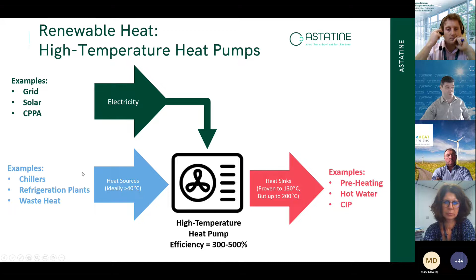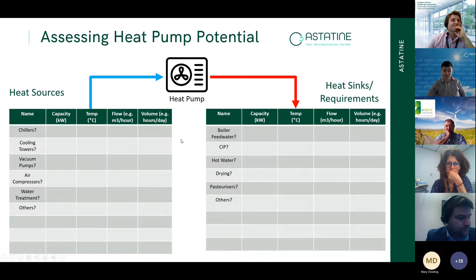I would say on the dairy facilities, these are very typical of the sources and sinks that we find. So on the sources, we find things like chillers, cooling towers, vacuum pumps, air compressors, water treatment plants, and then we quantify what amount of heat we can absorb from those different sources. And then on the heat sink side, we're looking at things like boiler feed water, CIPs for cleaning, hot water systems, drying, so we can preheat air for drying, pasteurizers, and any other uses of water up to about 120, 130 degrees that we can find on site.